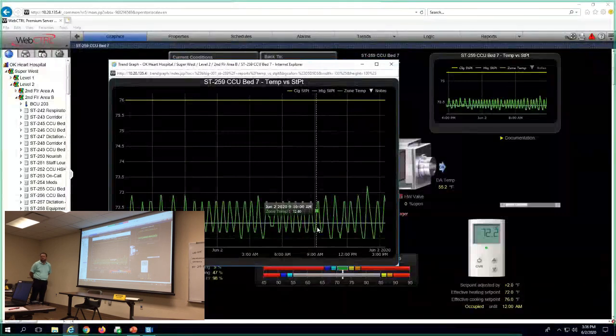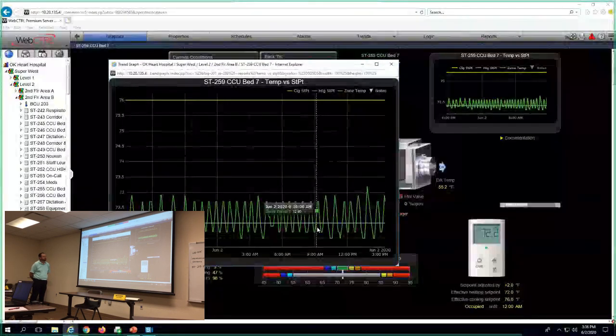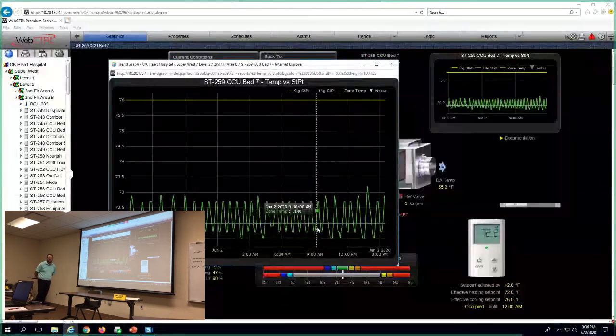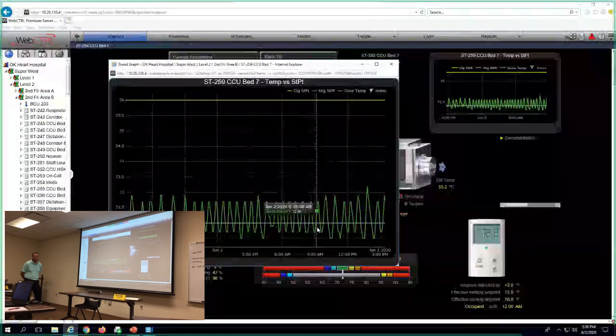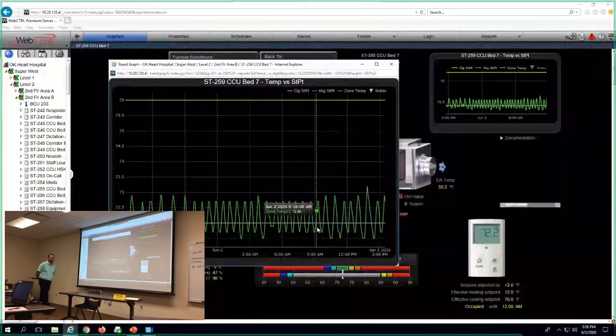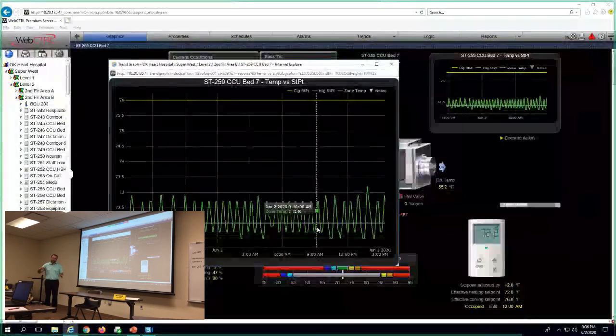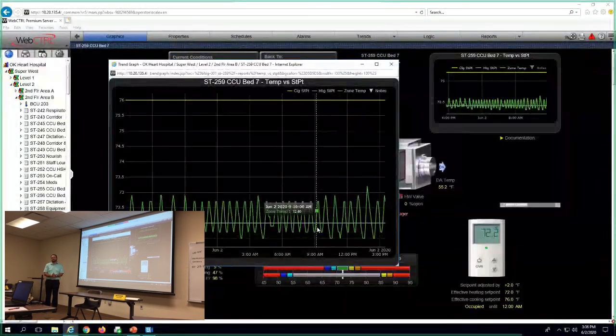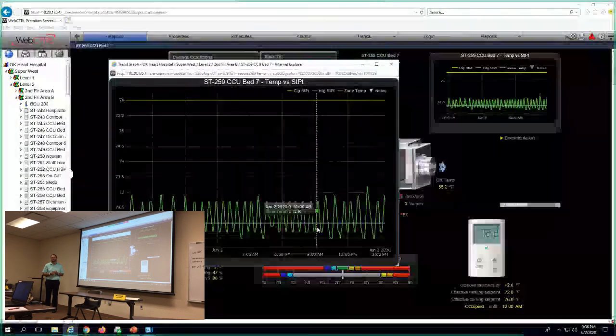But it's also worth thinking about how the space is naturally heating or cooling at any given season, right? That's why this one's laying at the bottom, because either the door's open and the corridor's cold, so it's naturally driving that room down. This building's doing a lot of reheating, because the temperatures on our air handling units are like 53 degrees. When we've had some rain and humidity, when we've tried to compensate for humidity, it drives the temperature down to try to reheat the space back.